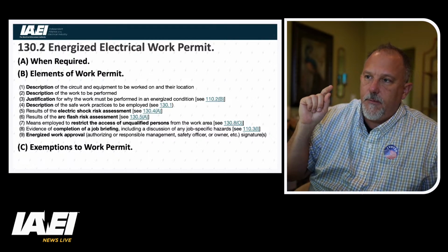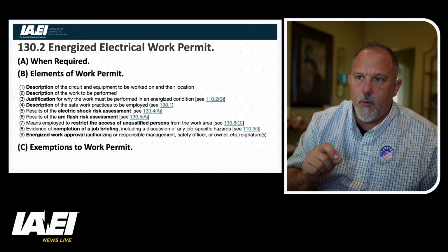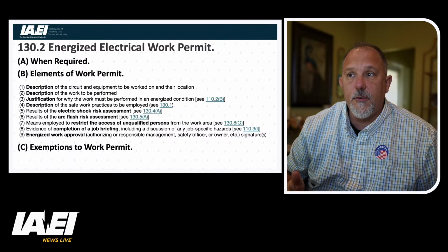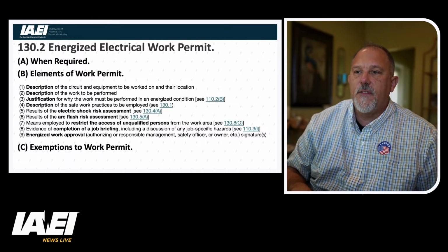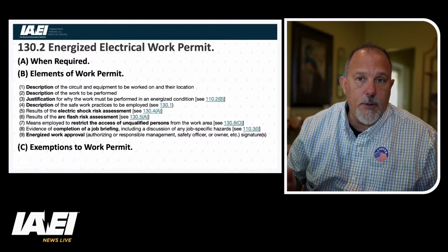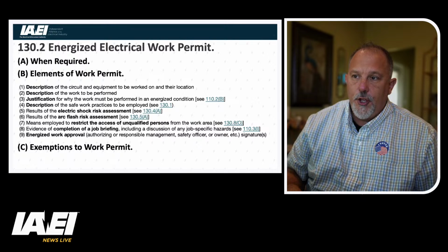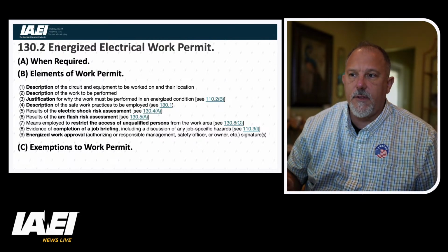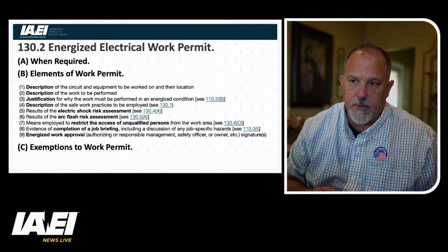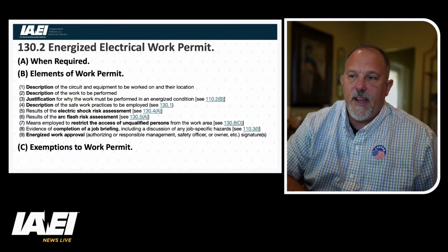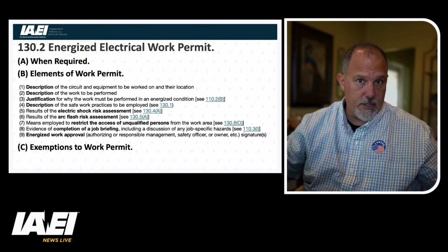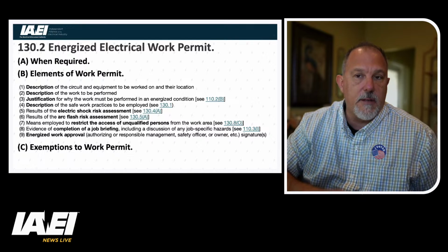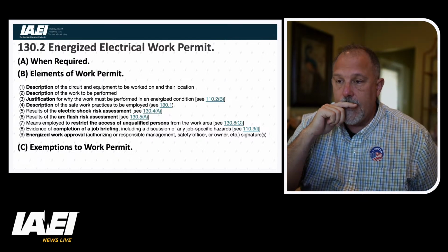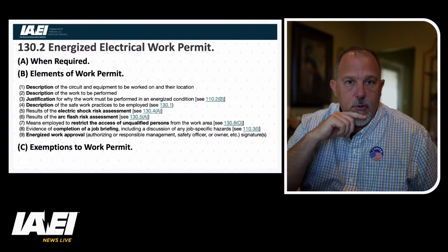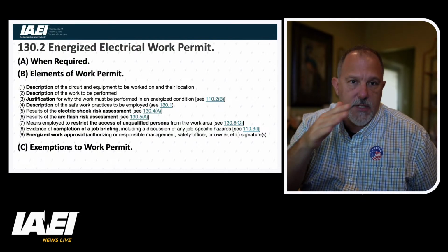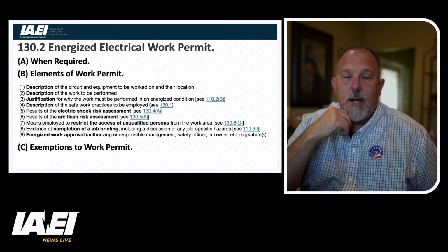You have to have a description of the circuit and the work to be performed. You have to have justification on why you're going to do the energized work. You have to describe all of the safe work practices that you're going to employ. You have to conduct and report the results of an electric shock risk assessment and an arc flash risk assessment. You have to have means employed to restrict access to unqualified persons, so those are your barriers. You have to have evidence of the completion of a job briefing, and then you've got to have documented approval with signatures of the energized work. That would be your permit.